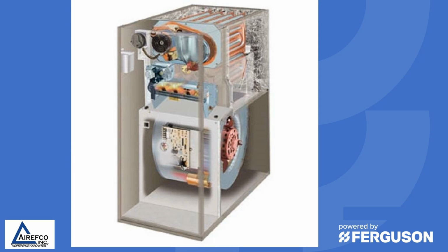After we've completed our initial observation of the furnace installation, we want to open up the doors and continue working on the furnace. One of the first things that we want to look at is the inducer motor. When a furnace is given a call for heat, this is the first device that starts up.